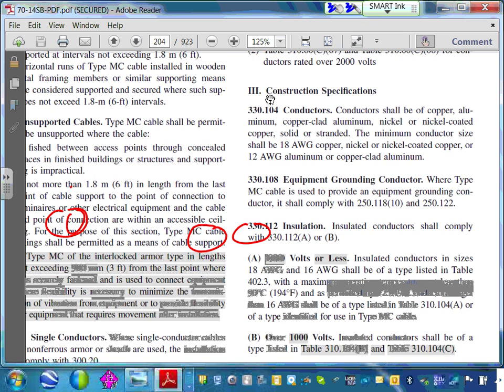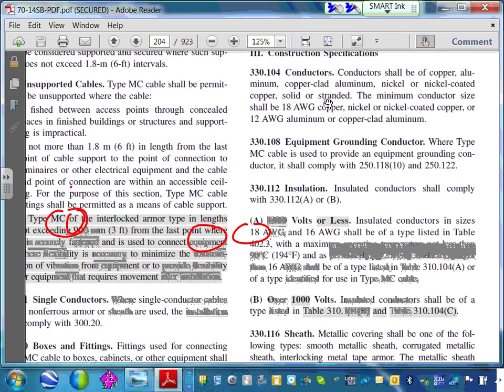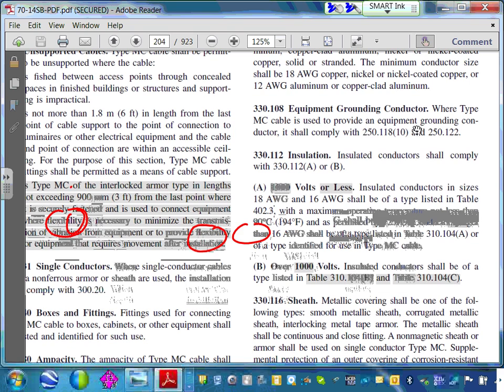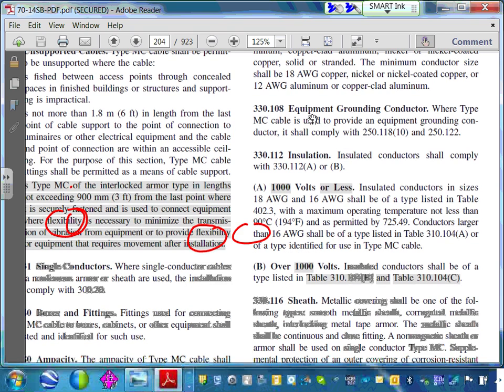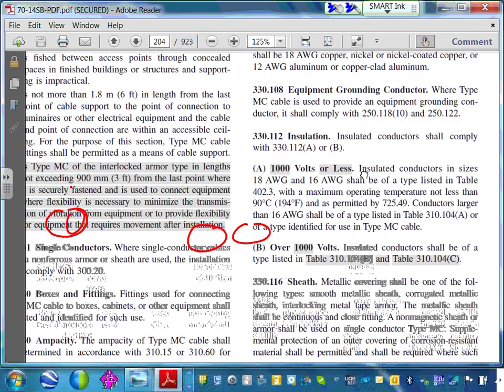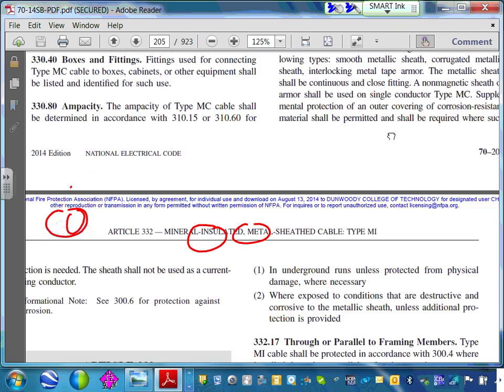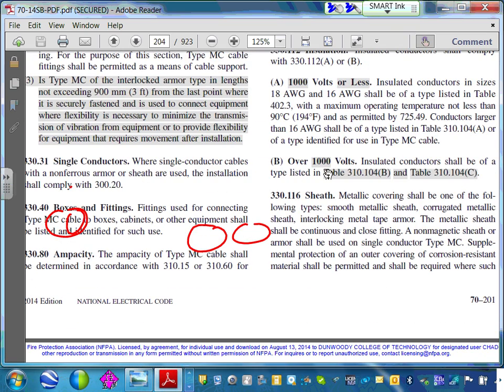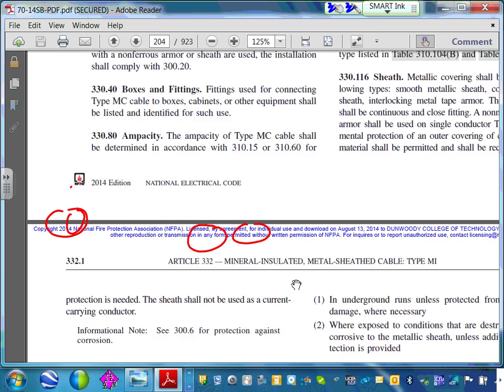The last thing is about construction. Can you see how they construct it, how many conductors, what the maximum size is, whether it has an equipment grounding conductor, the insulation, and remember, there's an over-1,000-volt insulation type too.